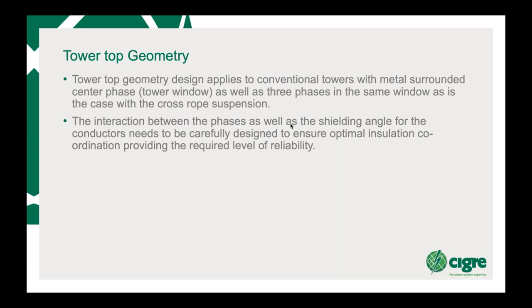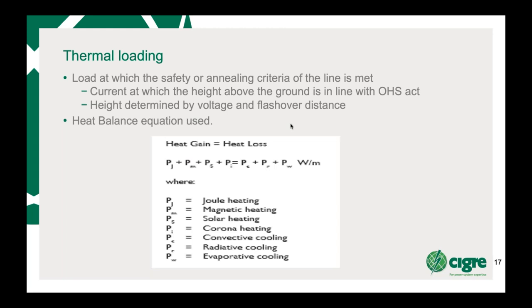Looking then at the AC line design, we're looking now at thermal rating. As was covered before, the thermal rating is a load at which the safety or annealing criteria of the line is met. So the safety criteria links to the height above the ground, in line with our OSH Act. The height is determined by voltage and flashover distance.